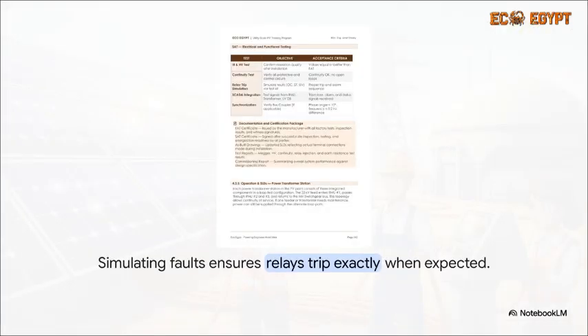Notice how the SAT specifically zeroes in on worst-case scenarios. Field engineers use these specialized test kits to artificially inject highly dangerous faults like severe overcurrents or earth faults directly into the system. The whole goal is to make sure those precise protection relays trip the massive circuit breakers exactly when they are supposed to, in milliseconds, sending those vital timestamps back to the control room. It proves the safety loop is completely airtight.